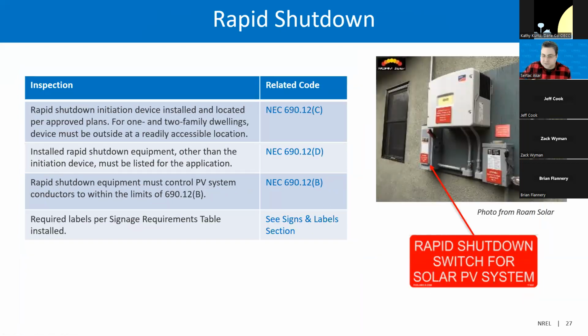Next thing to inspect is the rapid shutdown. For rapid shutdown, the inspector should check that the rapid shutdown initiation device is installed and located per the approved plan, and for dwellings must be outside in a readily accessible location. Installed rapid shutdown equipment must be listed for the application within the limits of the National Electrical Code 690.12(B), and labels should be per the signage requirements table as installed. You can see the labels here in this picture. They should be visible and displayed on the rapid shutdown device.